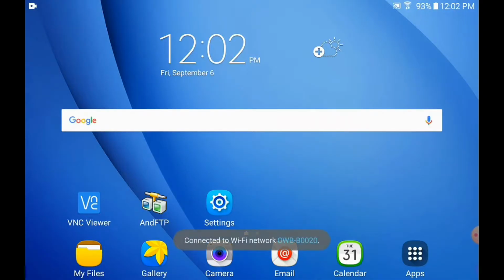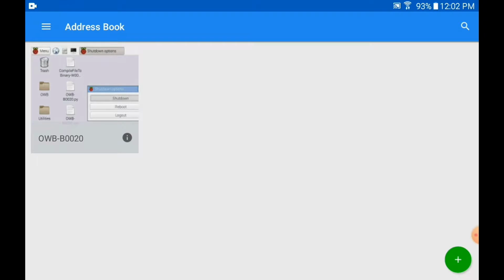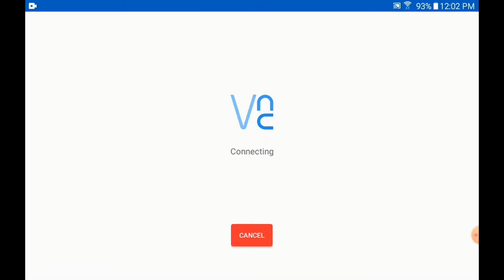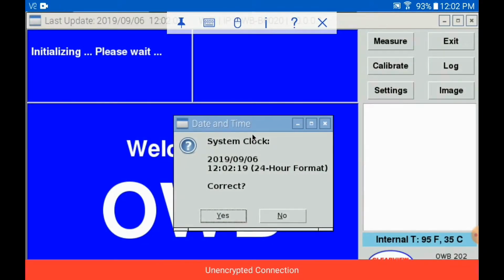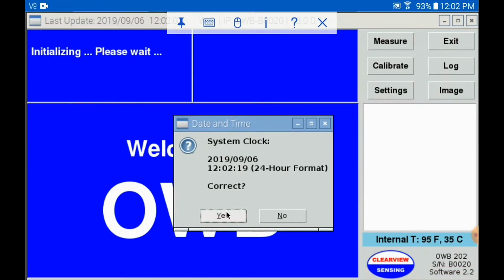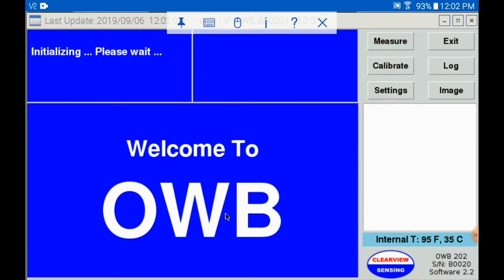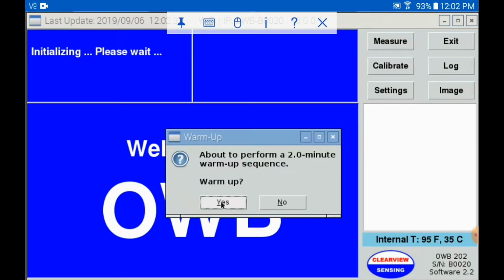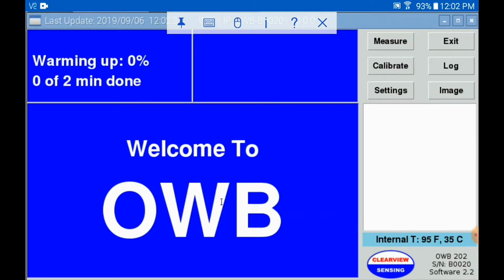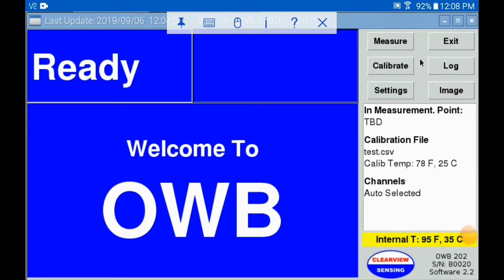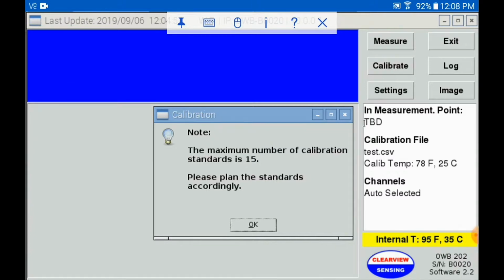Upon startup, the tablet will automatically connect to the OWB's Wi-Fi. VNC Viewer can then be used to connect to the OWB user interface. Once the system clock is confirmed as correct, OWB will prompt for a warm-up sequence. Please click Yes to warm the unit up. Calibrate can now be selected. Notes on calibration will appear with important information.